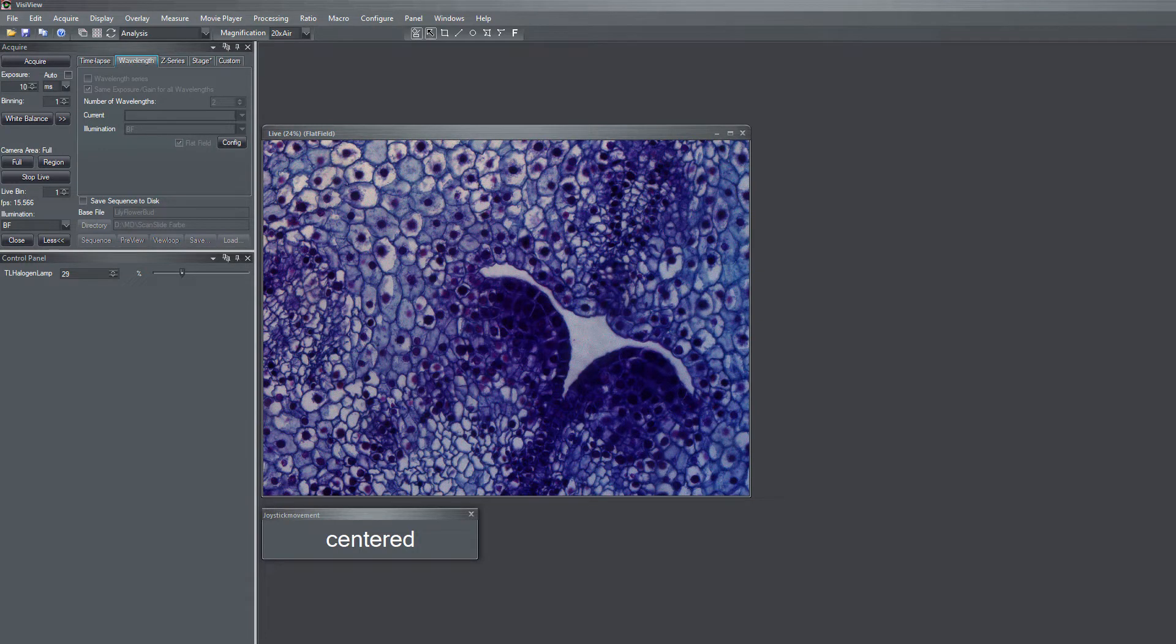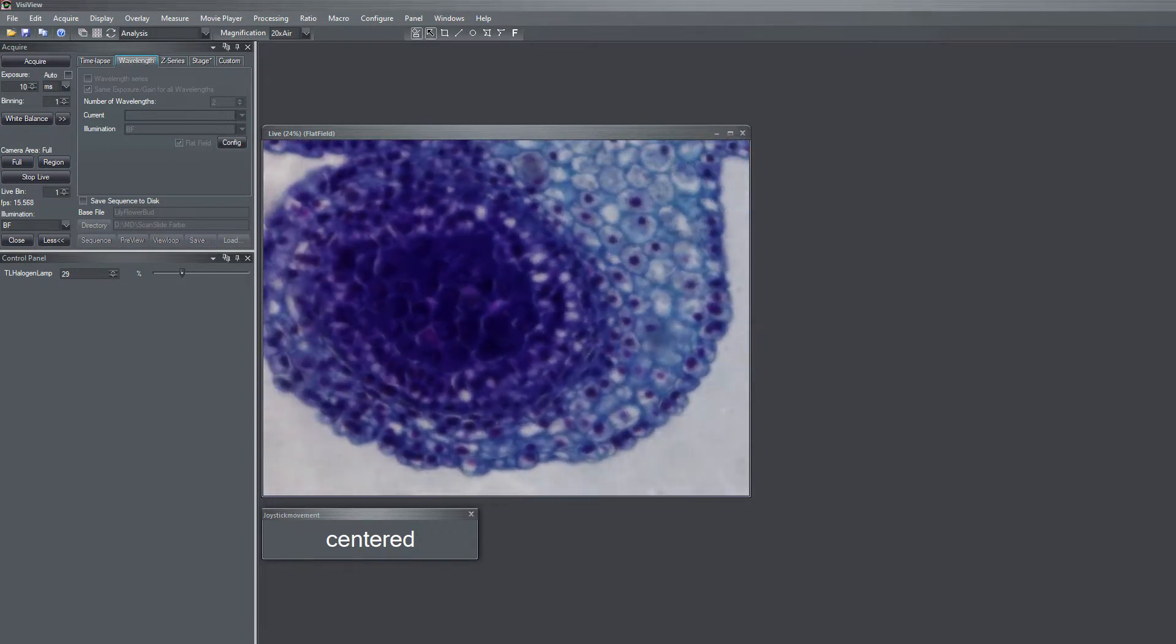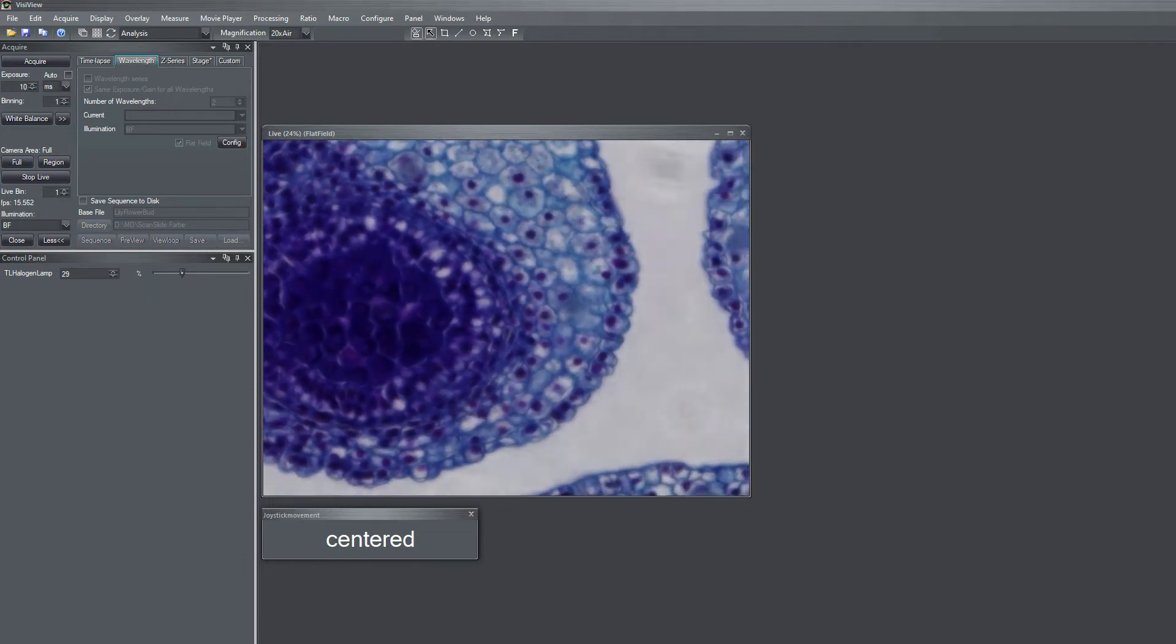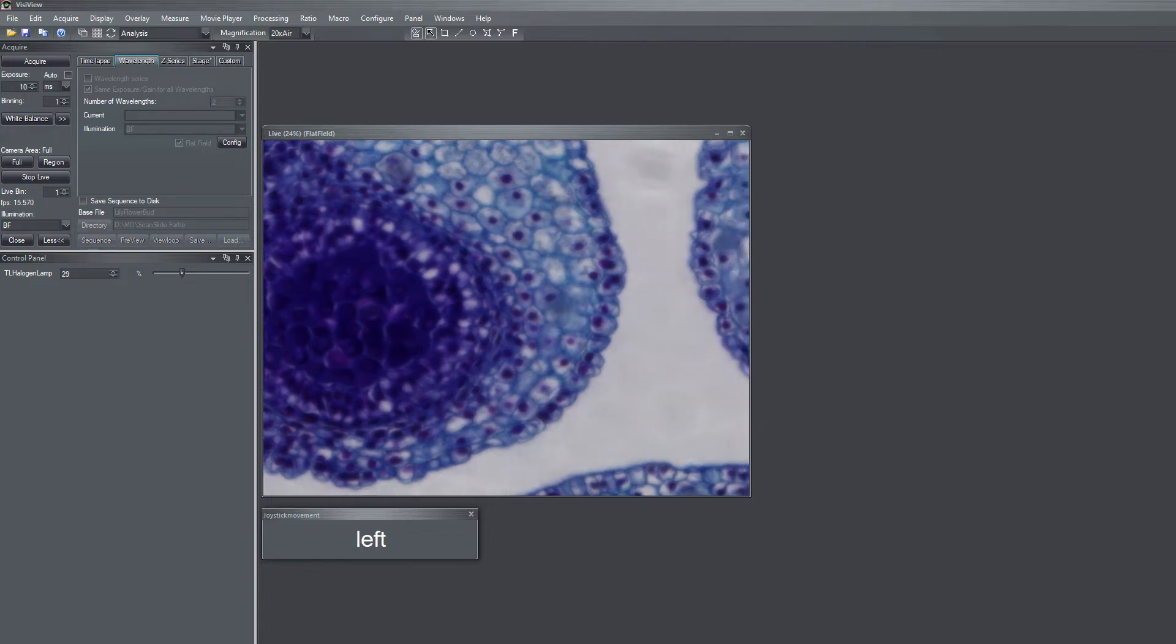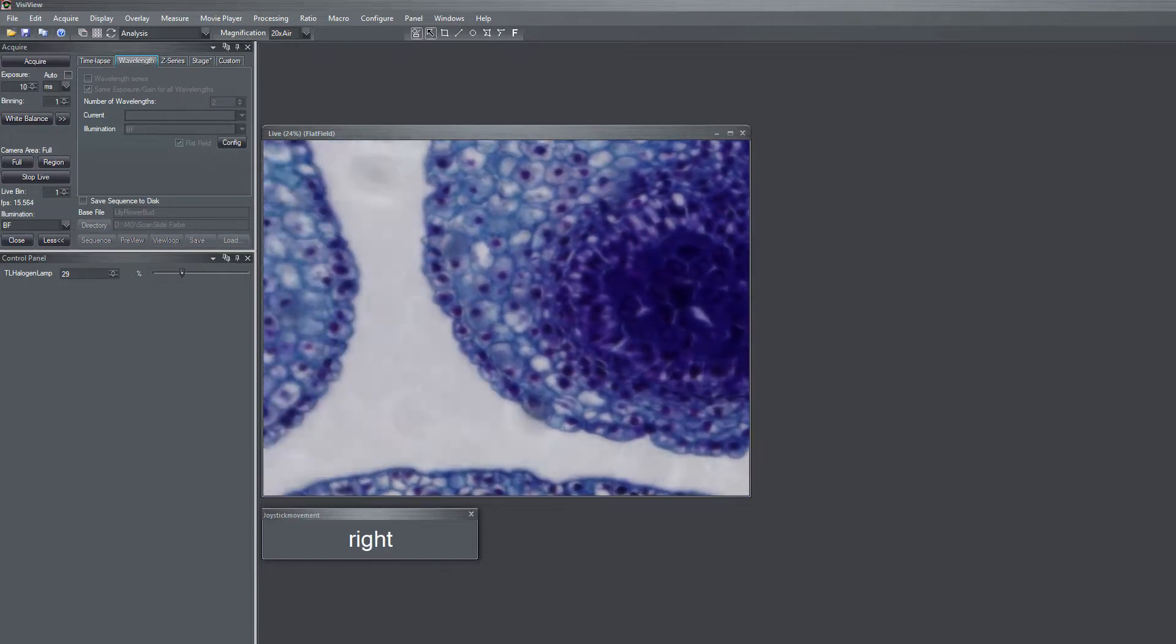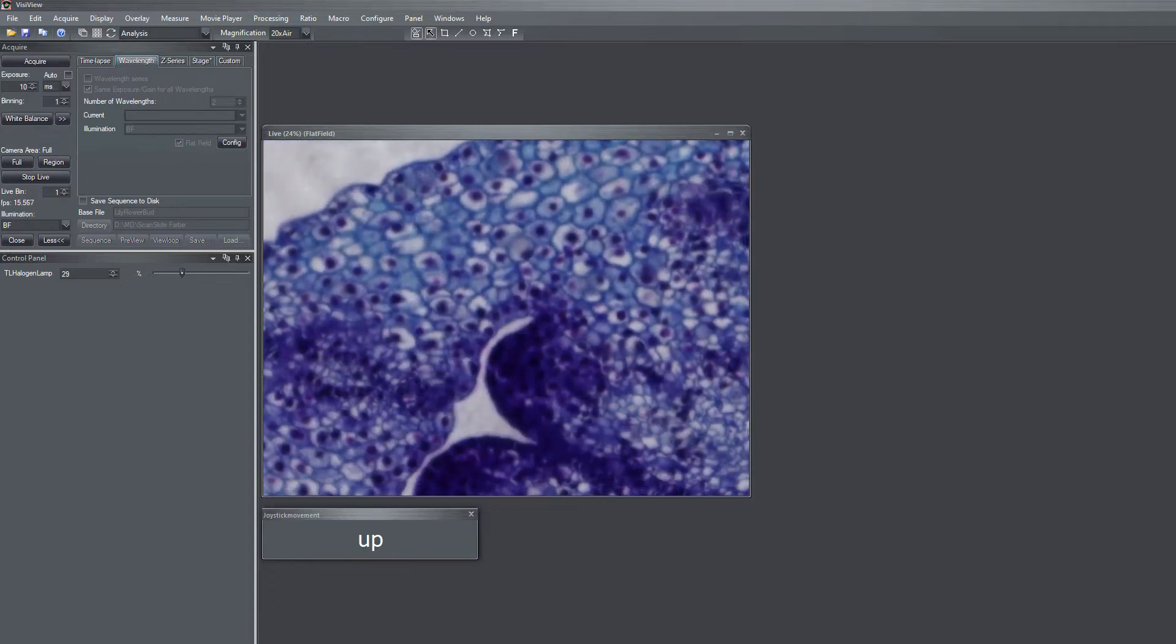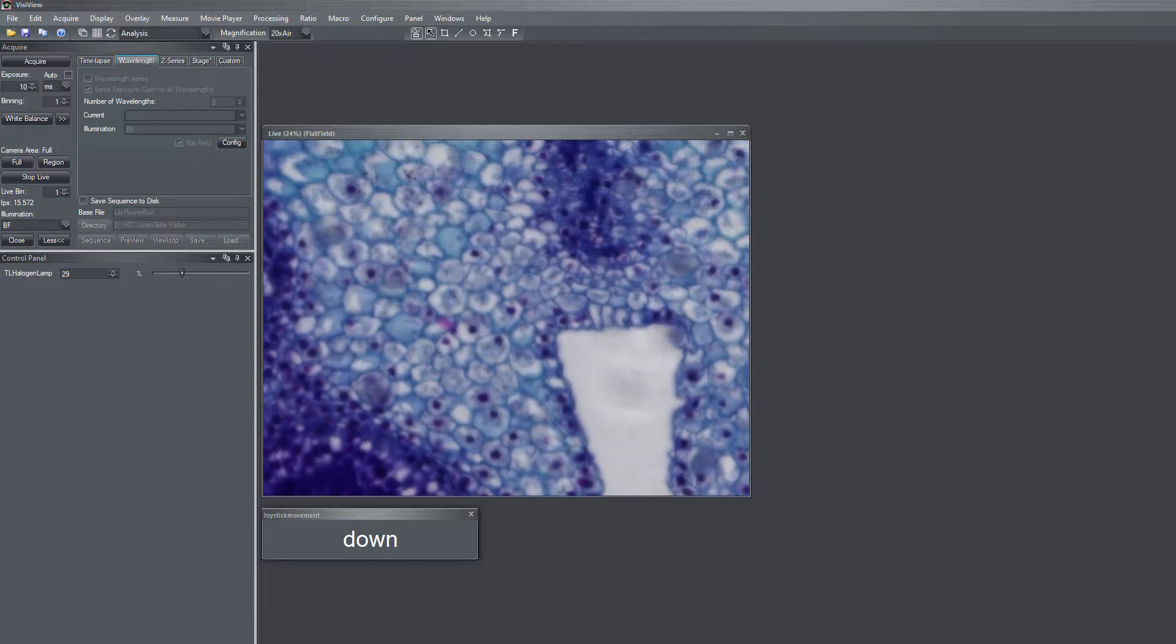So what you then should do is rotate the camera by 90 degrees physically, or if you have a monochrome camera, you go to camera configure dialog and rotate the camera by software. If you now move your stage left and right, up and down, you see that your sample moves in the same direction on the same axis, so the rotation is now properly set.